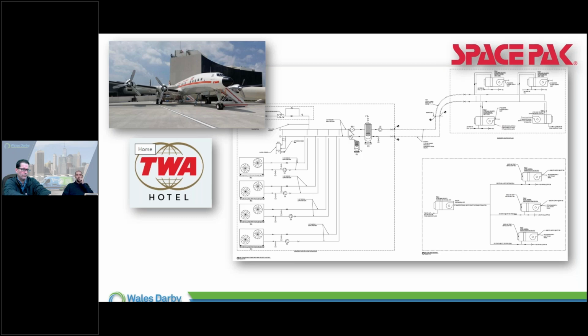So if we have heating and cooling simultaneously and we're pulling from two different tanks - maybe a fan coil unit's doing cooling and we're doing some pre-warming or floor conditioning with a heated tank - I can literally draw off of both tanks, and whichever one calls first, the outdoor unit will satisfy that and get it back to where it needs to be, then switch over to the next. I don't want to get too far into the weeds, but we can be creative. All the questions you're asking, I think we've already seen and pretty much have an answer for.